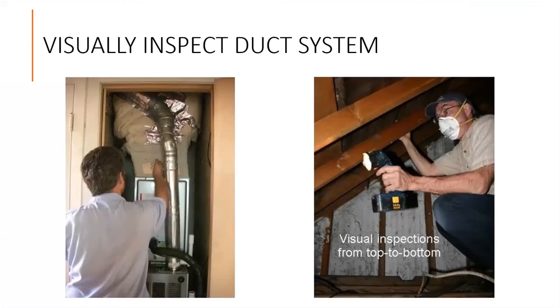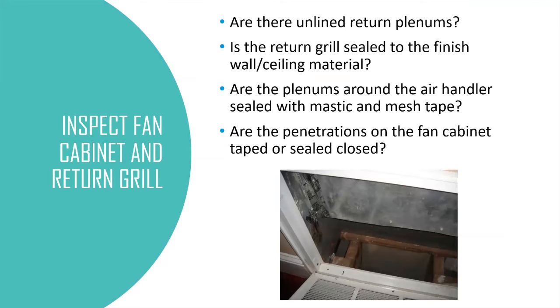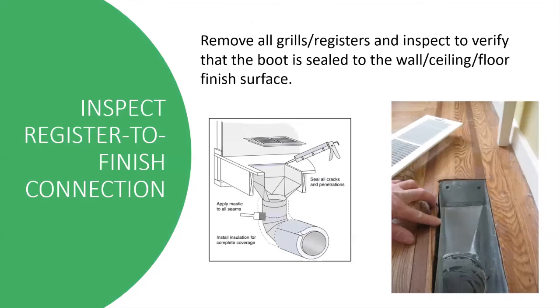You should be looking at the entire system from top to bottom. When inspecting the fan cabinet return register, check for the following: Are there any unlined return plenums? Is the return grill sealed to the finished wall or ceiling material? Are the plenums around the air handler sealed with mastic and mesh tape? Are the penetrations on the fan cabinet itself taped or sealed closed? When you inspect to verify if the boot is sealed to the floor, you'll likely find plenty that look like it's not sealed. You can use caulk to seal the boot to the floor, or fold aluminum tape from the edge of the floor down into the boot, where the tape on the finished floor can be covered by the register.